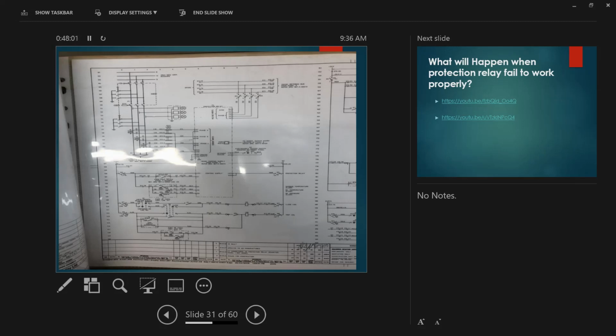Sometimes we have a hard time wondering why this one doesn't close. It will inhibit you from operating the breaker because it's not safe to close the breaker if your trip circuit is unhealthy. Normally they have a schematic monitoring this coil. I think this is the trip coil, TC. TCS, normally they call it, trip coil supervision. Normally they connect that one to one of the inputs of the breaker, just to monitor.